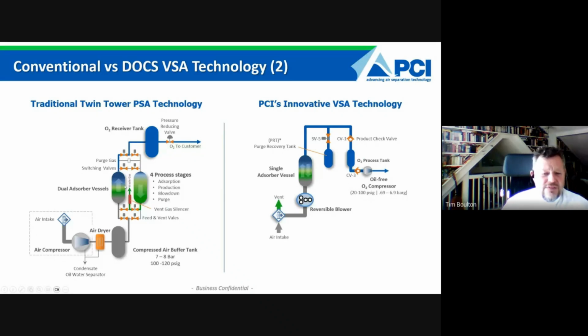What you don't see here, which is why this arrow is down, is that at the same time a part of that oxygen is being taken and is cleaning the other side. So this is generating and this is being cleaned or purged. It's like a balance. This is up, this is down. When this zeolite sieve is full of everything but oxygen and argon, this process through these valves then reverses, and then this side will generate the oxygen and this side will be purged. So this would be up, this would be down. This is why the technology is called swing.